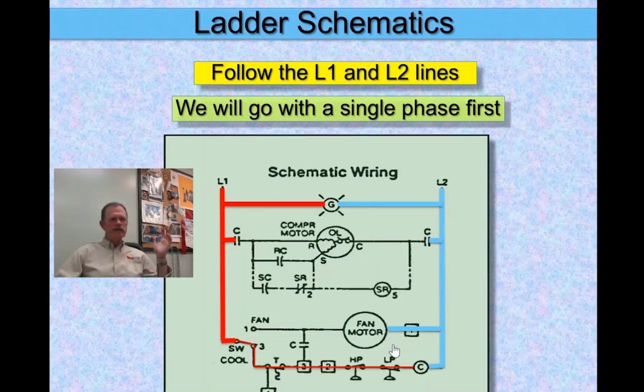Now, I should note, since the fan motor windings are conductors, that L2 actually would go all the way to this point, point number 1 where it says fan. L2 would be present all the way to that point. Okay, if you get that. If you don't get that, you can beat me up later.